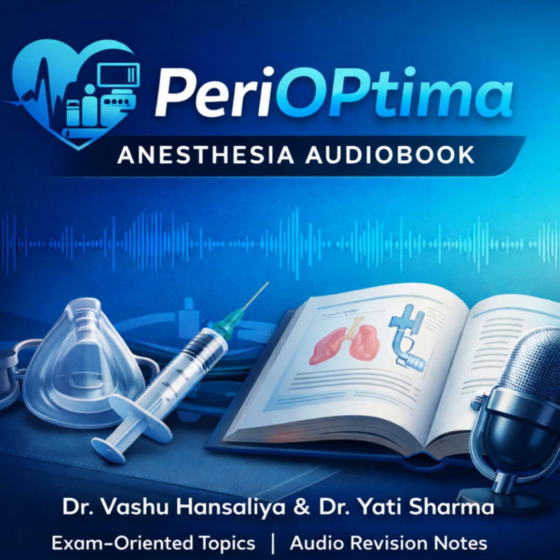Now here is a classic exam trap. If I, as the examiner, ask you, how long do you soak the fiber optic scope in Cidex? And you say 20 minutes, what have you just described? Disinfection. High-level disinfection. You're not wrong, but you haven't answered the question if I asked about sterilization. To achieve true sterilization, that is, killing the spores, you need to immerse that scope for at least 10 hours. 10 hours. I don't think I've ever seen a scope soak for 10 hours during a busy surgical list. Exactly. And that is why, in practice, many chemically sterilized scopes are technically only high-level disinfected.